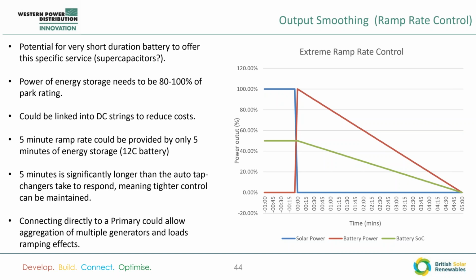If you did want to connect it directly to a primary, you could allow aggregation of multiple generators and loads and try and improve the overall voltage quality at the primary. So you would then monitor the primary load instead, and if the load suddenly dropped, you would increase, and if the load increased, you would drop to try and smooth out any voltage changes there. And you could do that more quickly than a tap changer could. It looks like this could be an opportunity for supercapacitors rather than the traditional lithium, which would suffer greatly at this kind of power.